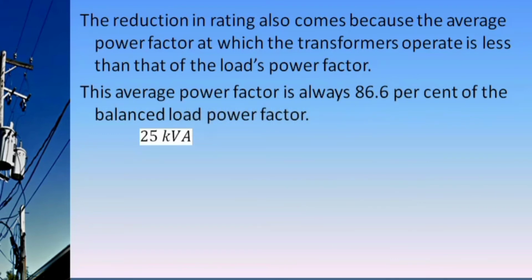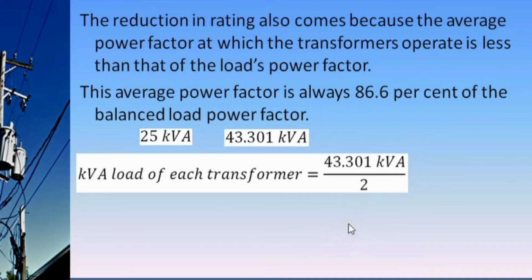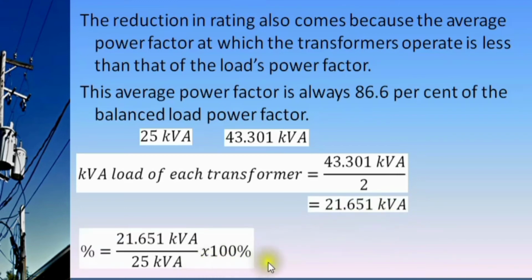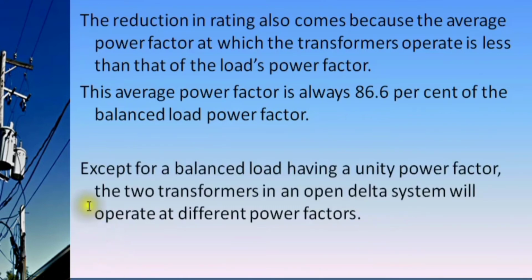Another example, if each transformer in an open delta system is rated 25 kVA, its open delta capacity is square root of 3 times 25 kVA, which will result in 43.301 kVA. Divide this by 2 to determine the kVA load of each transformer, we have 21.651 kVA. And divide this value by 25 kVA times 100%, we still have 86.604%.